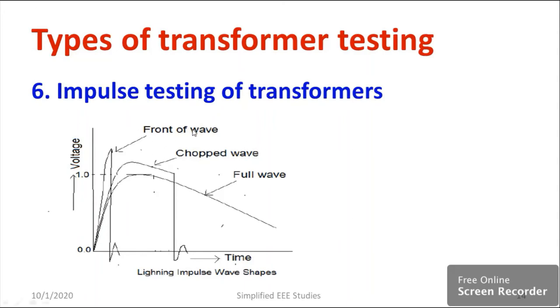We need to generate different types of impulse waveforms, for example front of wave, chopped wave, and full wave. By adjusting the wave front and wave tail resistance, you can generate these waveforms to test the transformer insulation. During lightning and thundering, these kinds of waveforms are generated. The voltage versus time graph shows different impulse wave shapes — if you observe the wave front time and wave tail time, they will be different for each type.